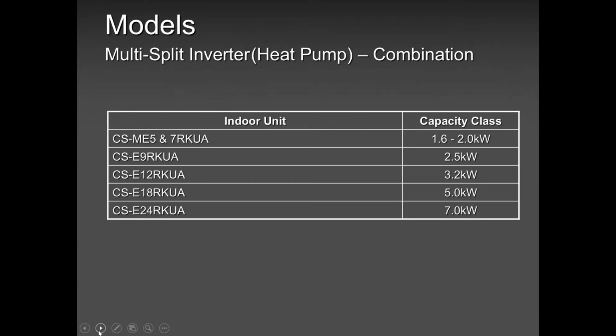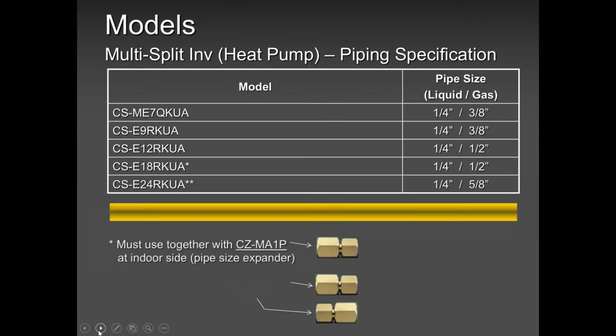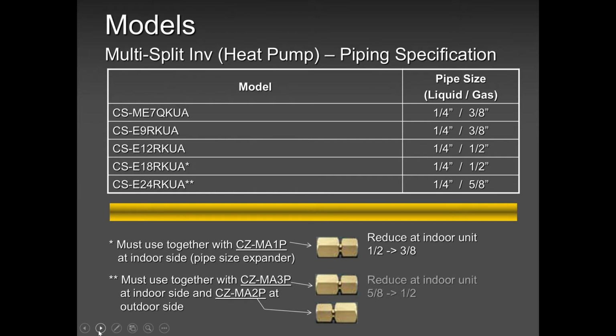Okay. Now, this is so important, guys. This section is so important. Why? Because as far as our competitors and other manufacturers are concerned, they run their pipes based on the indoor unit piping size. If the indoor size pipe was 5/8 and quarter, they run all the way down to 5/8 and quarter, and they do the adjustment at the outdoor unit.